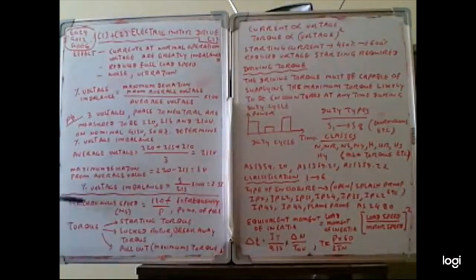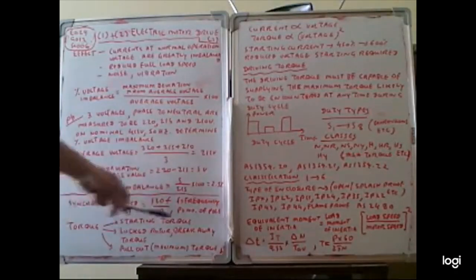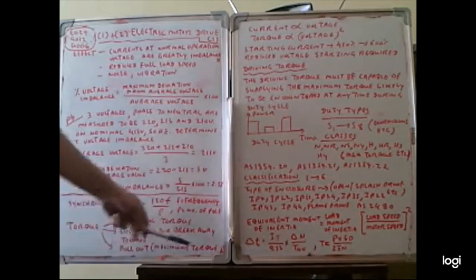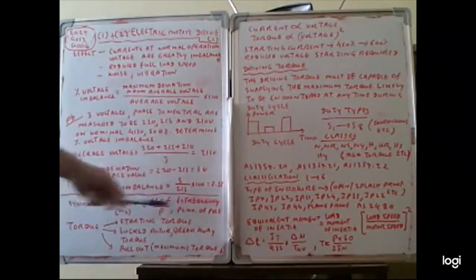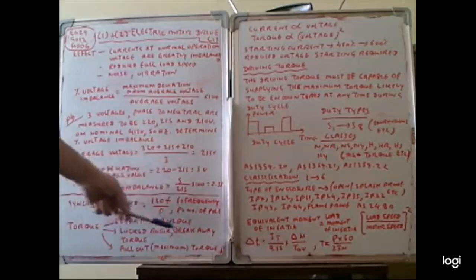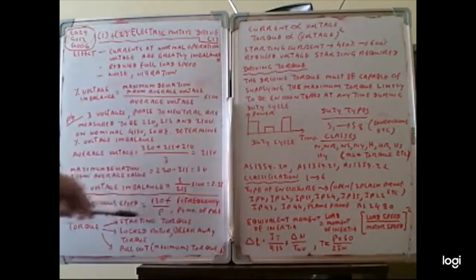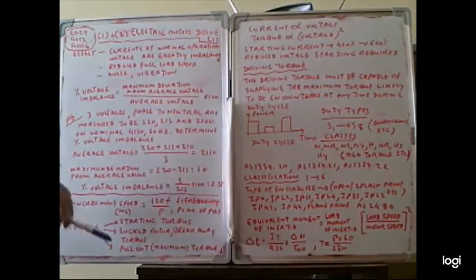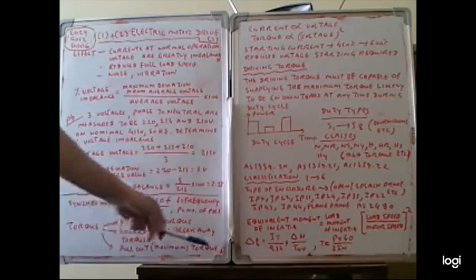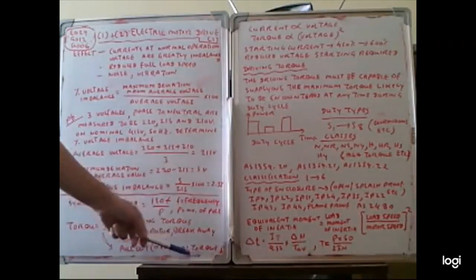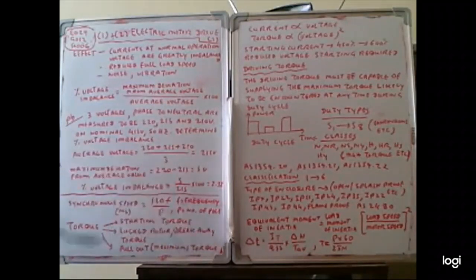Motor torque can be the starting torque, locked rotor torque, breakaway torque, and the pull-out maximum torque. Starting torque means that when the motor is starting, the motor needs to overcome the motor inertia, so the starting torque has to be great. Locked rotor torque is when we lock the motor rotor and measure the torque required to lock the rotor. Pull-out torque means the maximum torque. When the motor is running, the maximum load that can be supplied by the motor depends on the maximum torque.